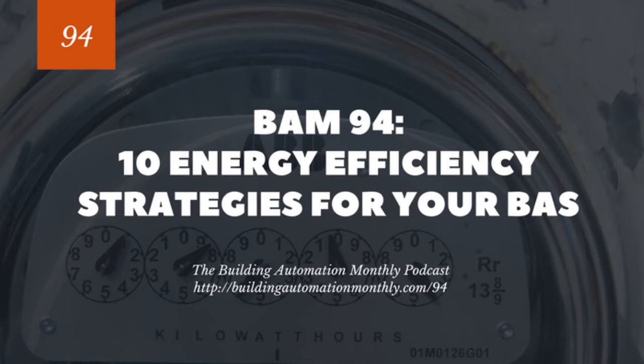Now, way number 2 is to set the proper changeover temperatures. You see, quite often you'll have a summer-winter changeover where at 60 degrees you'll enable the chilled water plant, and at around 55, 50 degrees, you'll enable the hot water plant. But that's not necessarily optimal.